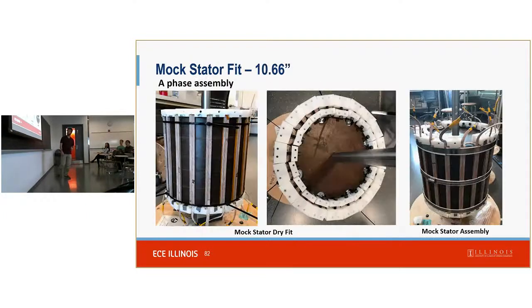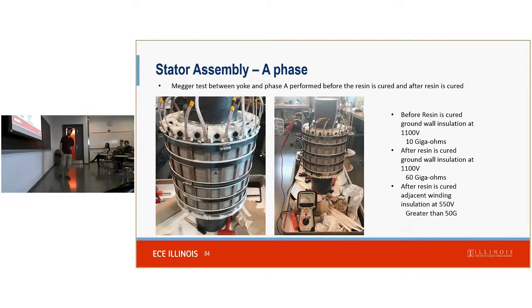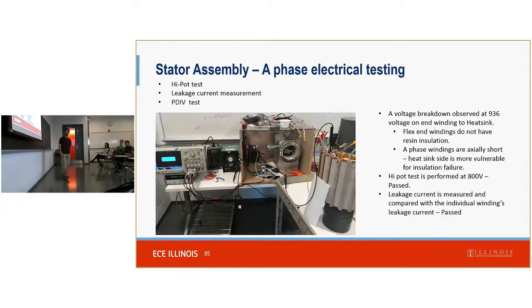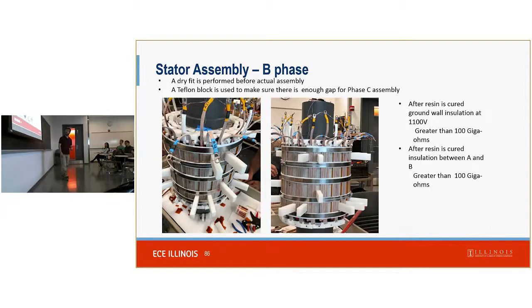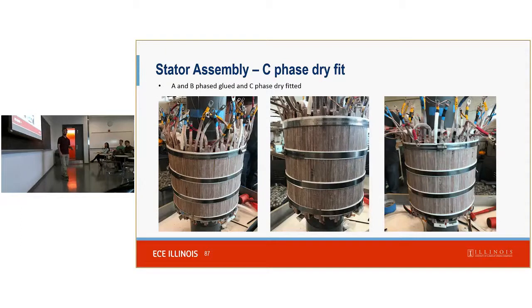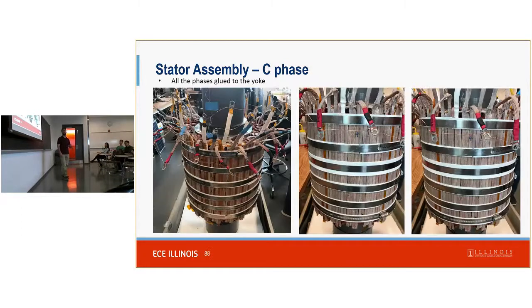And so the next step then is to begin to attach the coils to the stator. We started with another practice to make sure that once they were stretched, they fit better, and in fact they did. And then we actually glued them in place onto the stator, onto the yoke. After doing that, we tested the insulation between each coil and the ground cylinder, and found that the current that was allowed through with this Megger test was small enough that it indicated we had sufficient insulation. And then we repeated the process with the B phase and C phase, doing a dry fit and then a final glue fit.